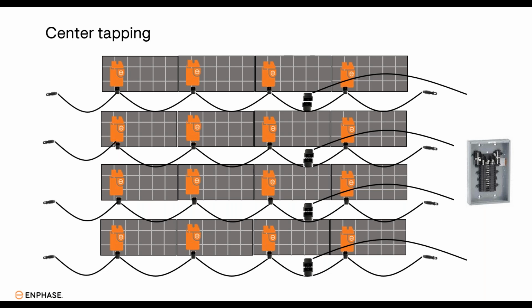If you were to take a length of 12 microinverters and pull power off one end of that QD cable without using the center tap connector, the voltage rise will become quite high, which in turn will shut off several of those microinverters. So you'll be losing production and the system will not be balanced for it to be working properly.